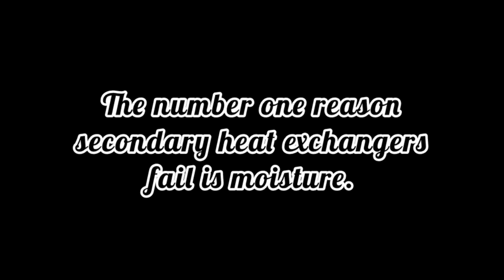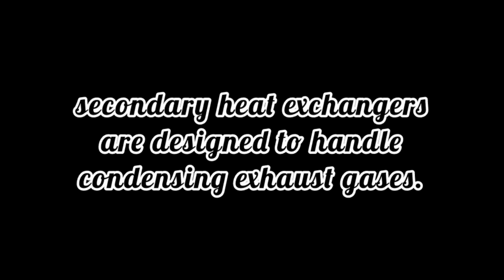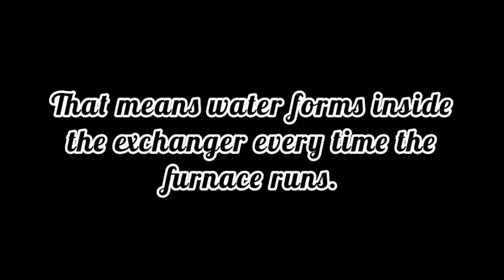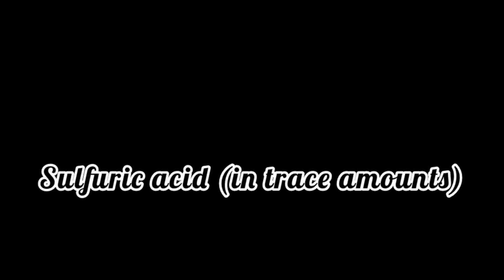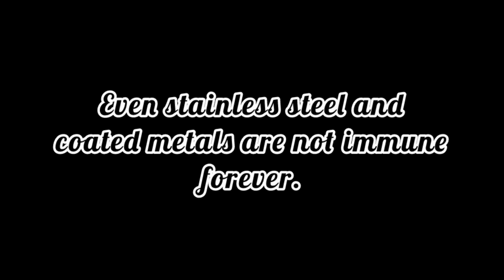Step 2. Why moisture is the biggest enemy. The number one reason secondary heat exchangers fail is moisture. Unlike primary heat exchangers, secondary heat exchangers are designed to handle condensing exhaust gases. That means water forms inside the exchanger every time the furnace runs. This condensation is not pure water. It contains carbonic acid, nitric acid, and sulfuric acid in trace amounts. These acids slowly eat away at the metal surfaces from the inside out. Even stainless steel and coated metals are not immune forever. Over time, protective layers break down, allowing rust to form. Once rust starts, it spreads quietly, often unnoticed until damage is severe.